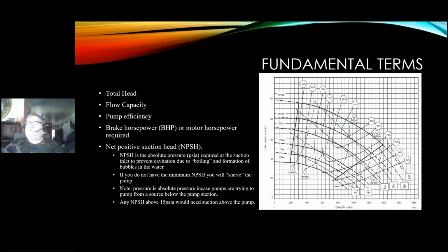Net positive suction head. This is what we're talking about, the cooling tower with not enough water coming in. It's the absolute pressure. Each one of these curves represents how much pressure you need coming in, PSIA, required at the suction inlet to prevent cavitation, boiling, and formation of bubbles in the water. I have more trouble with this on projects than anything else, which is strange because it's usually based on either a bad selection or somebody put a resistance in, or in most cases, a strainer is blocked where it's picked up garbage.